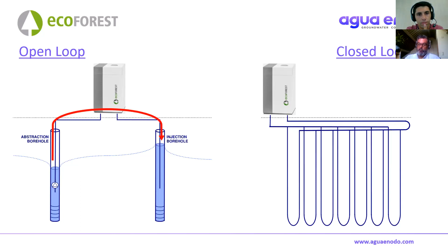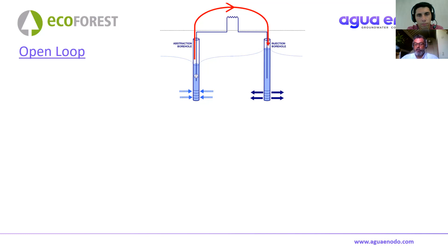There are a number of different types of open loop. We've got the conventional dedicated abstraction borehole and dedicated injection borehole, where we take water out of an aquifer, pass it past the plate heat exchanger, and put it back into the source aquifer. Depending on the loads we have different flow rates, and if you need more flow with a bigger load, you have more boreholes - so single borehole systems or multiple borehole systems.